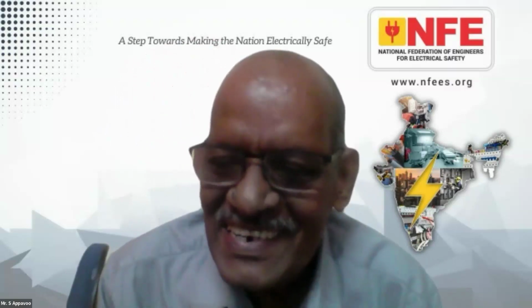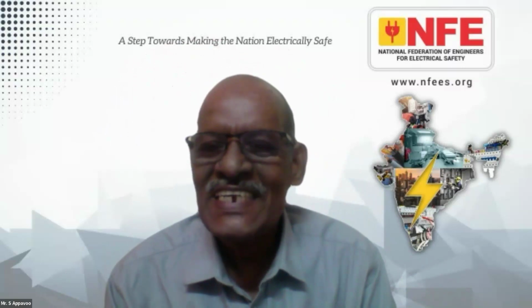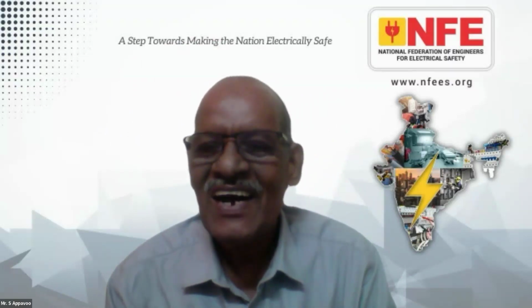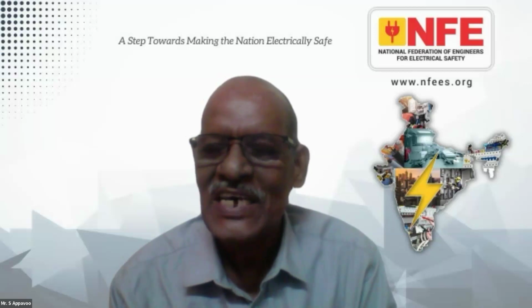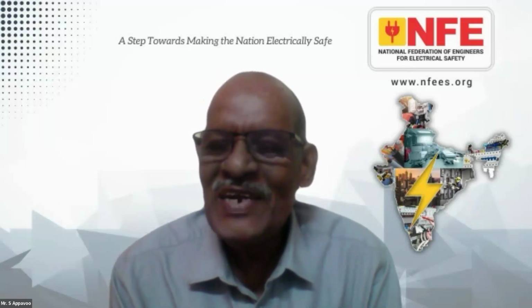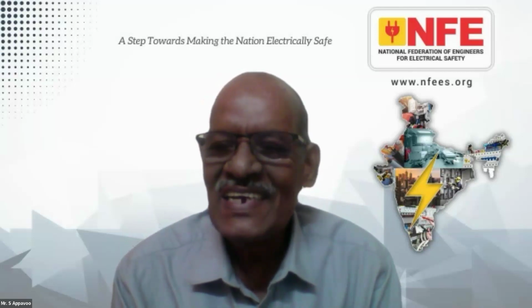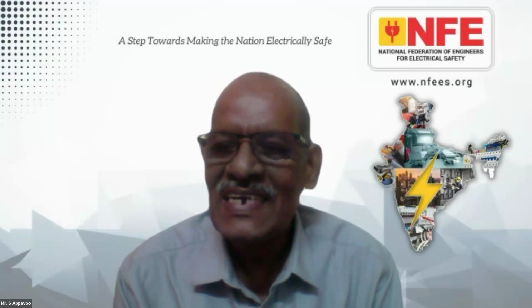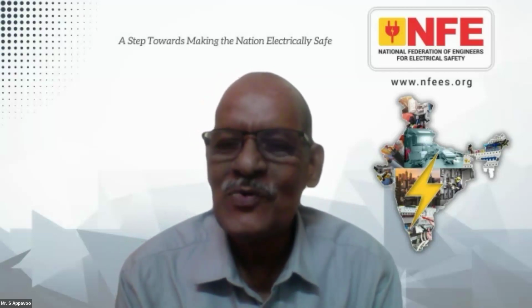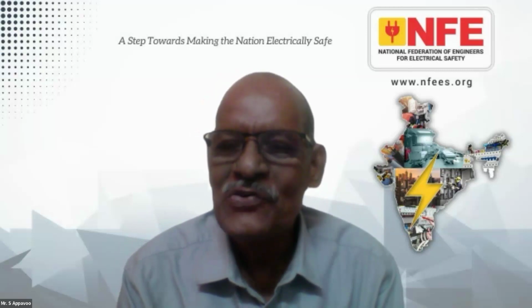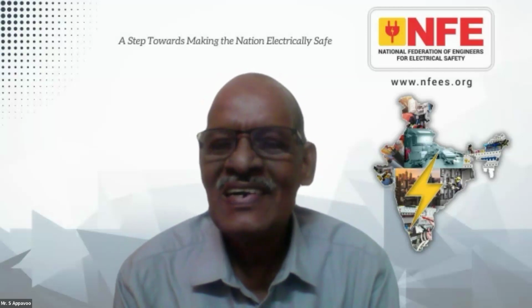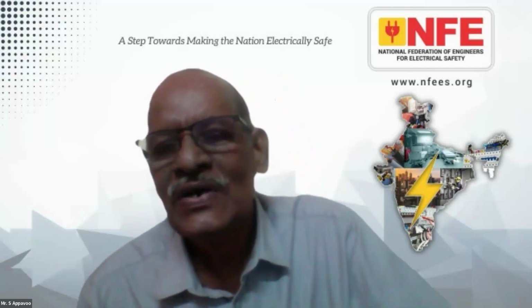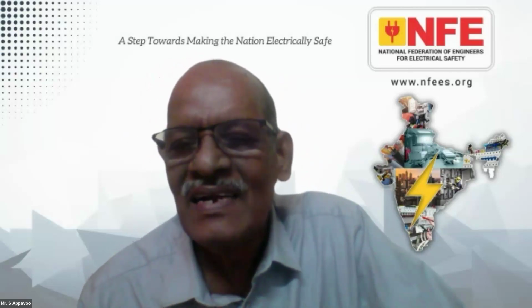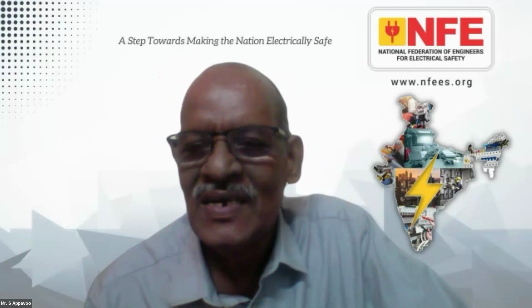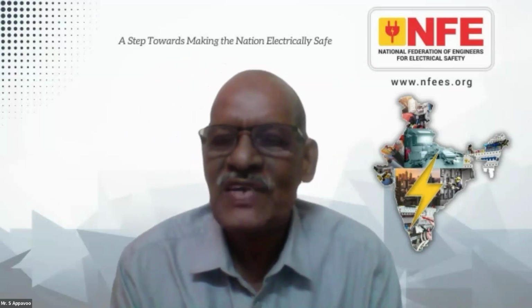Ms. Pallavi, what I can suggest is, if you are in a medical facility, you can be an HR person or administrative person. If something goes wrong with the medical device or some IT device in a data center, in a medical institution you ask the biomedical engineer, and in a data center you ask the utility engineer how it can happen. Ask them to conduct a study and put forth their views on how it happened. You can drive them. You need not know the fundamentals of harmonics. Ask them to measure and understand whether it exceeds the permissible limits, and how it is actually affecting your equipment.